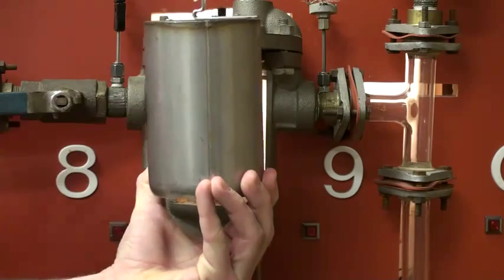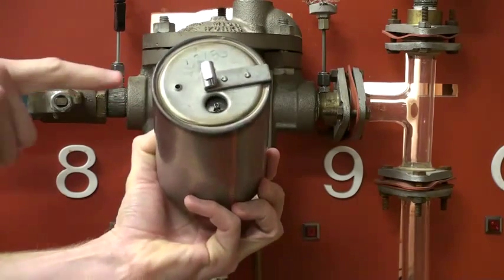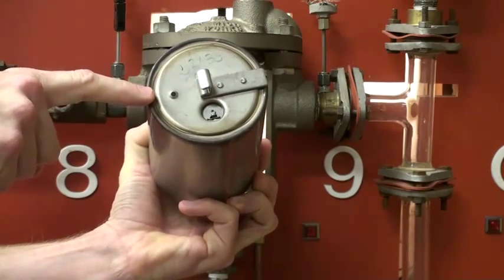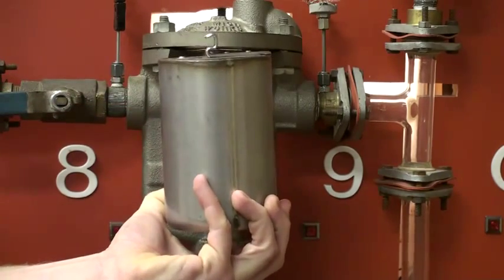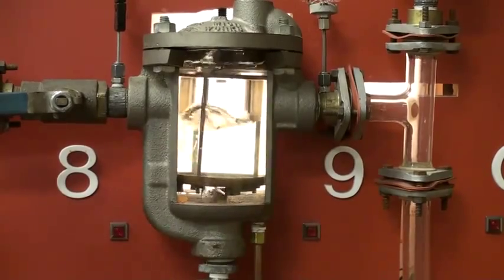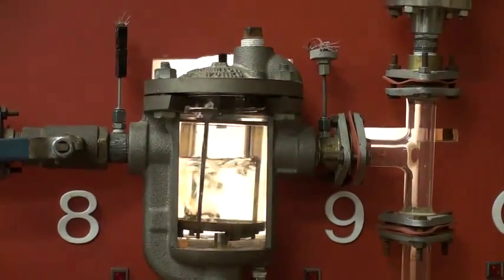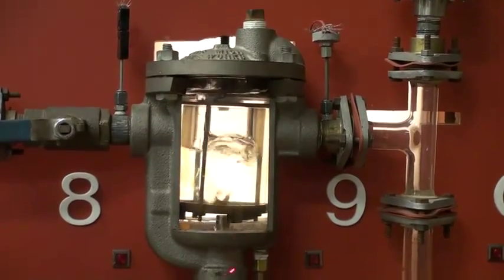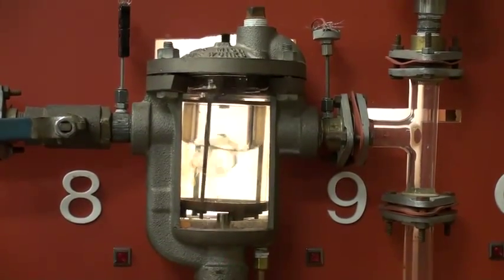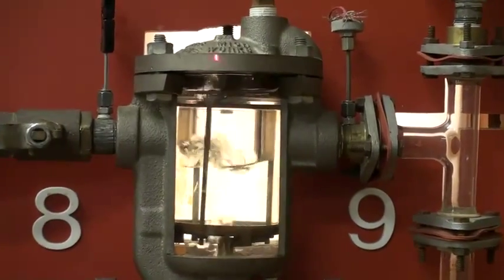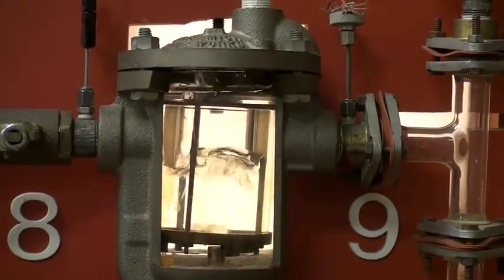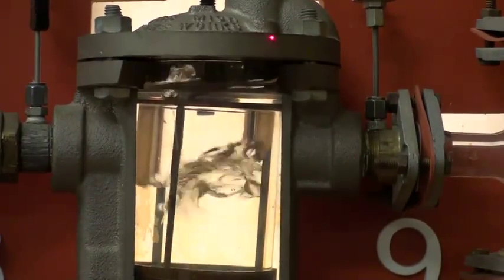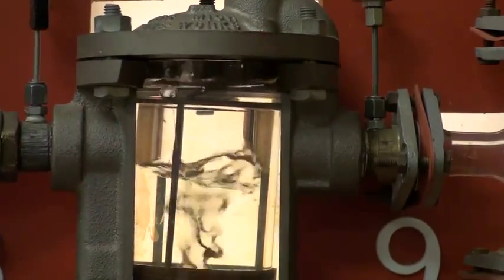the bucket. A small orifice called a bucket vent is located at the top of the bucket to ensure that non-condensable gases cannot be trapped inside the bucket. Steam, air, and condensate enter the trap through an inlet tube beneath the bucket. Air and condensate are discharged through an orifice at the top of the trap. At the orifice is a valve that is linked by a lever to the top of the bucket so that the valve is closed when the bucket is in the up position.